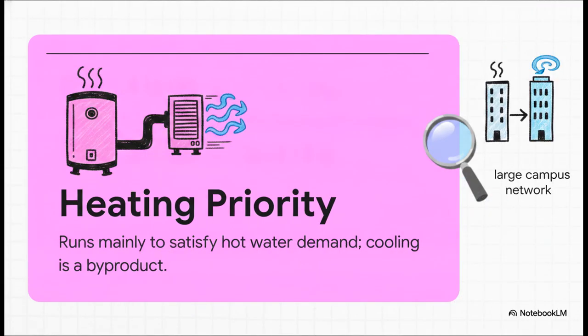But on the flip side, we have heating priority. Here, the machine runs mainly to satisfy a demand for hot water. The demand for heat entirely drives the operation, making the chilled water a useful byproduct. You see this quite a bit in large campus networks, where the excess chilled water can easily be piped over to a neighboring building that needs it, even if the primary building doesn't.